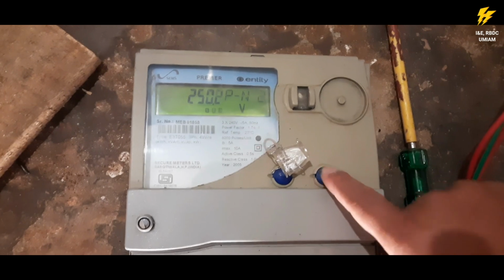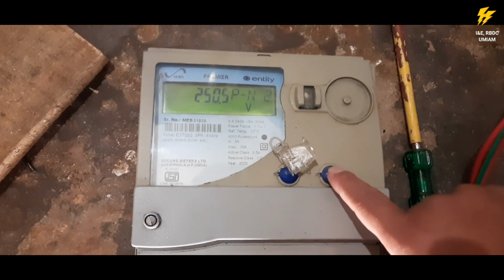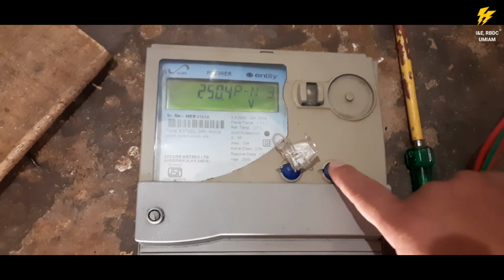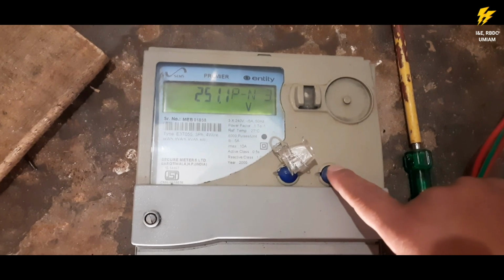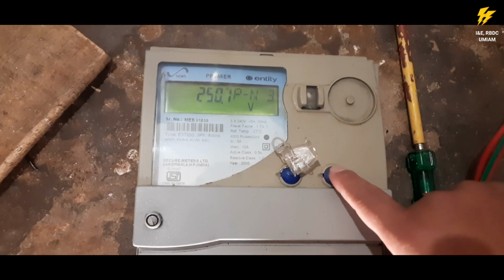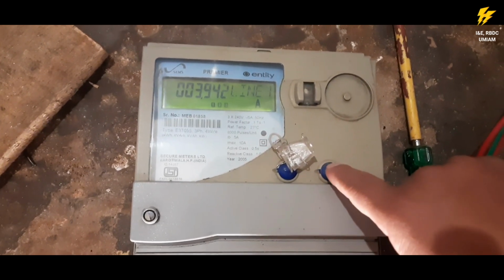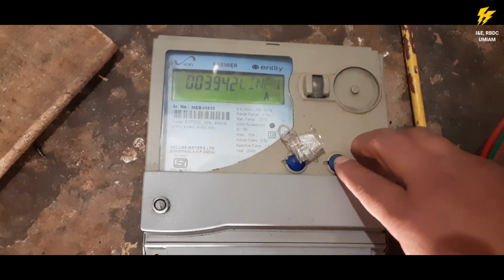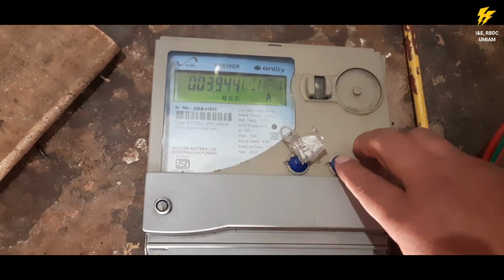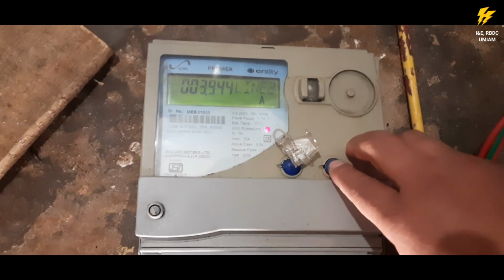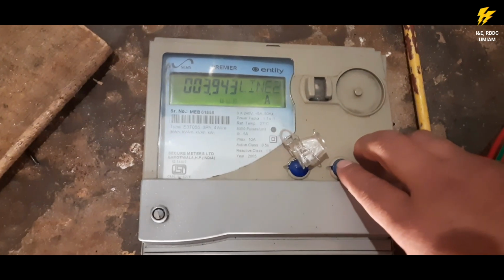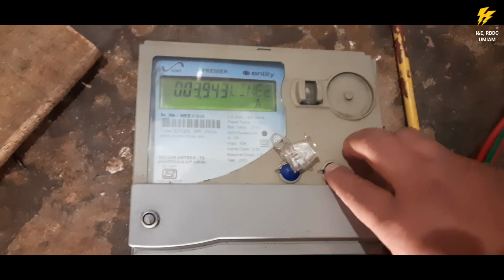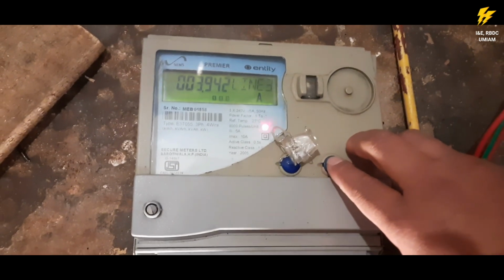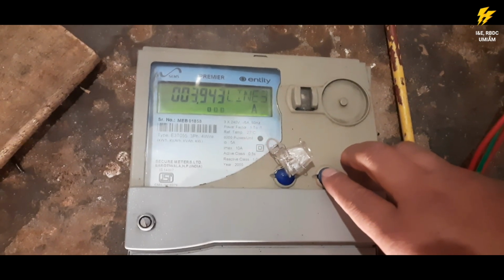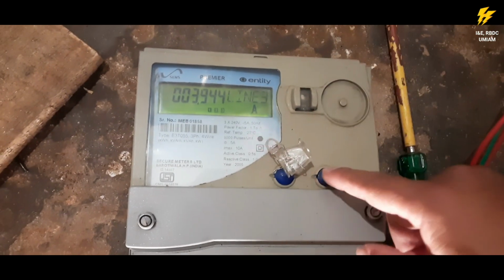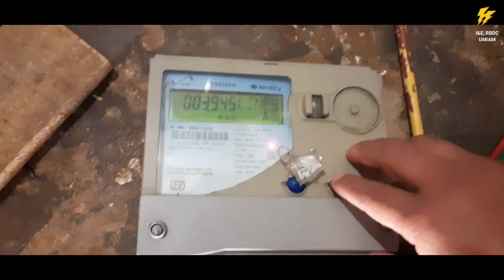Pn1 means R phase voltage, and then Pn2 is Y phase voltage, which is 250, because I'm using the same voltage, it will be almost the same. And this is B phase voltage, 250 volt, and then this is line 1 current, which is 3.9. Like I said, it will be less than 5, 3.94 ampere. And line 2 is also the same, because I have connected in series, 3.94 ampere. And then line 3, B phase current, is also 3.94 ampere, because they are matching, because I'm using the same current only by looping.